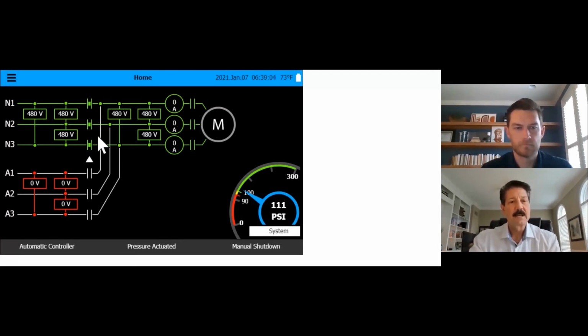As we go from the secondary of the magnetic breaker, we have another voltage reading. This voltage reading is more for us, for people that are really looking and observing for troubleshooting. This second reading of 480 volts is taken from the line side of the contactor. If you go further to the right, you'll see a couple of vertical contacts. There are 3 of them. They're open. That is our contactor, designating that it is currently open. So the voltage that we see, the second reading of 480, 480, and 480 per phase, is on the line side of the contactor. What does that prove to us? It shows that we have continuity through both of the circuit breakers.